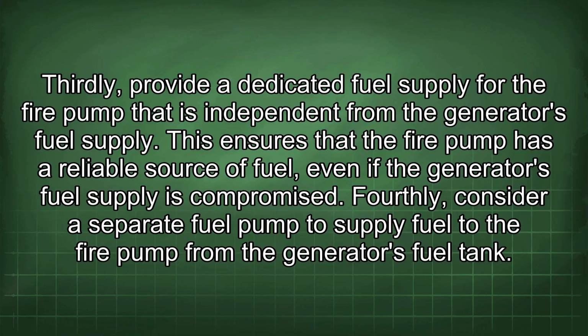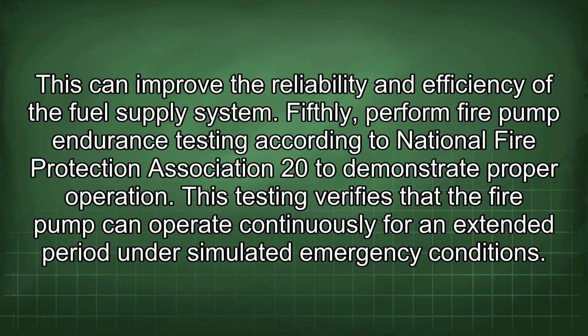Fourthly, consider a separate fuel pump to supply fuel to the fire pump from the generator's fuel tank. This can improve the reliability and efficiency of the fuel supply system. Fifthly, perform fire pump endurance testing according to National Fire Protection Association 20 to demonstrate proper operation. This testing verifies that the fire pump can operate continuously for an extended period under simulated emergency conditions.